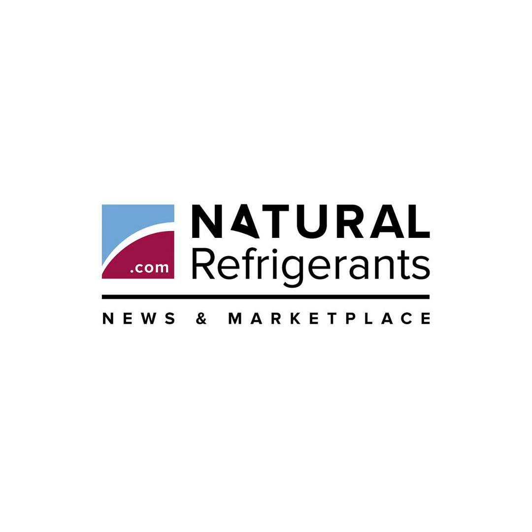However, in the U.S., the use of propane in HVAC is limited by UL's most recent 4th edition of the 60335-2-40 standard, which restricts the use of R290 to 114 grams, 0.25 pounds, for all HVAC's residential and light commercial applications. The ASHRAE 15 standard also significantly restricts A3 refrigerant use in residential and commercial applications to less than 150 grams, 0.33 pounds, with any larger amount requiring approval by a local jurisdiction's code officials. Last October, UL held the first meeting of a new Technical Harmonization Committee, THC, to develop the fifth edition of UL 60335-2-40.